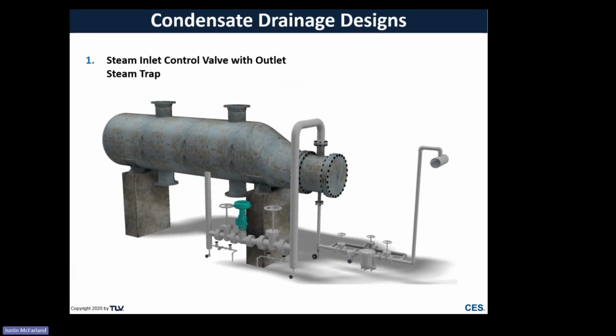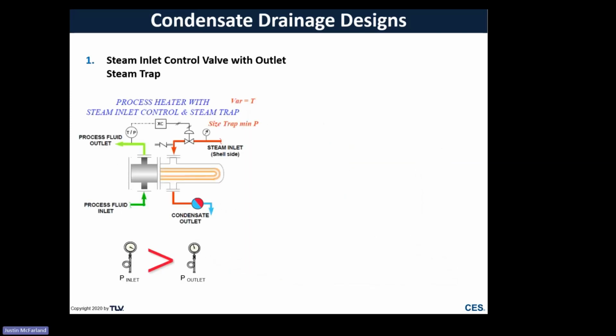So I want to briefly get into different types of control systems, what those look like, and maybe some of the drawbacks that you would see with them. First, a very simple one: the steam inlet control valve with an outlet steam trap. Pretty simple. The objective here is to modulate the temperature of the process by effectively modulating the steam temperature or the pressure. You can see here we've got an inlet control valve with a controller looking at the process outlet temperature, and a steam trap here. As long as we have positive differential pressure, so our inlet pressure is greater than our outlet pressure, then we can drain condensate using a steam trap and life is great.